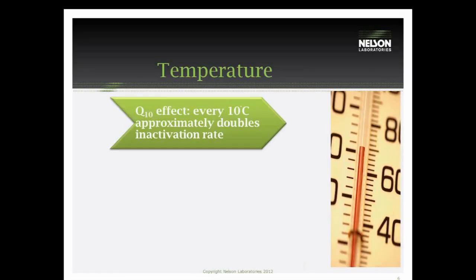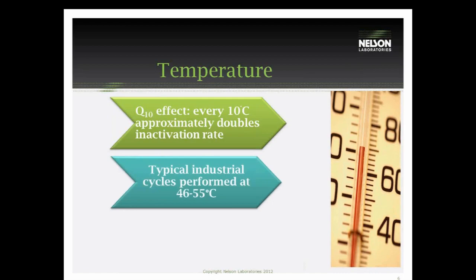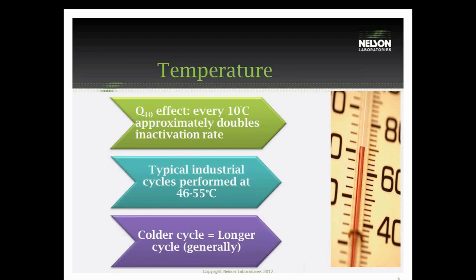Temperature has what we call a Q10 effect. For every 10 degrees that you increase the temperature, you approximately double the inactivation rate of the organism on the device. Typical cycles are between 46 and 55 degrees Celsius. We can sterilize at lower temperatures, but this generally is going to increase your EO dwell time and makes for a longer cycle.